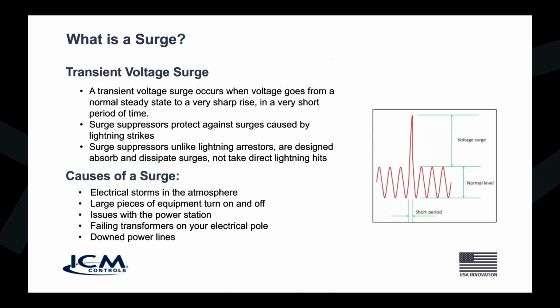So let's talk about what a surge is. So if you can see it from the diagram on the right, you got your normal voltage going along there nice and steady. Then all of a sudden you got that giant spike, right, at a very, very short duration. So a transient voltage surge occurs when the voltage goes from a normal steady state, like we see in the diagram, to this giant sharp rise in a very short period of time. Now the surge suppressors protect against these type of surges.